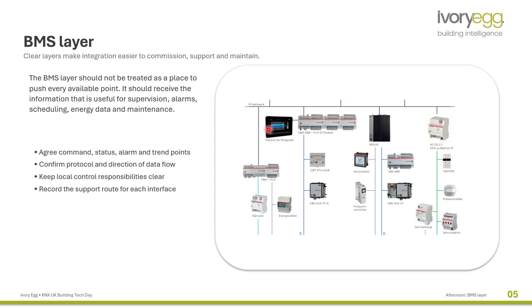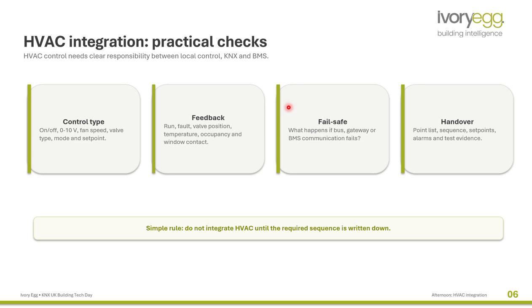So look at this BMS topology. You can see here KNX is located in the control and field layer. Field layer is the layer that we communicate with the physical layer of the building. Some person touches the button. This sensor detects the movement. This actuator closes and opens the circuit. And all of them go to the controller. In the controller, the data is manipulated locally. But above the controller it goes to the supervisory level. So these are some things that make the project a bit hard.